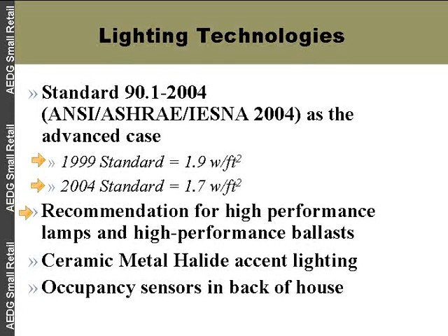We also changed the technology in the 90.1 lighting guides from halogen IR incandescent lamp to a ceramic metal halide lamp source. It is a more costly lamp, but we are seeing some really great energy savings and significantly longer life out of that lamp.